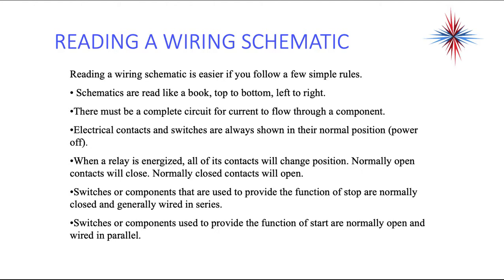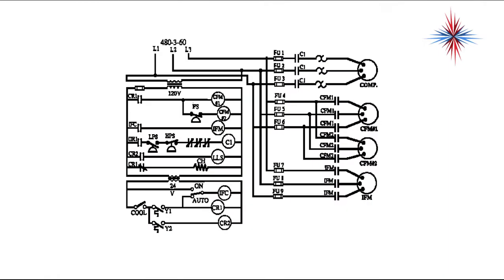If we go back to my original schematic, this is shown in its normal position, which means it is not powered, and this is just how it's wired. So again, if we're looking at the last rule, switches that are used to provide start are shown in their open position. So again, I have a contact here. It's normally open, that's how it's shown. Nothing is running. No voltage is passing. No current is passing.